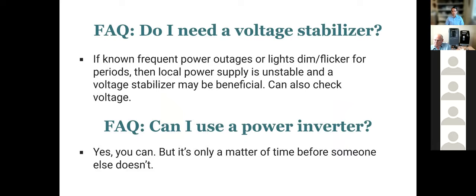So I mentioned this voltage stabilizer issue. A lot of people ask, how do I know if I need a voltage stabilizer? If the setting where the concentrator is going to be used experiences frequent power outages or commonly has issues with lights dimming or flickering for periods of time, then there's a pretty good chance that the local power supply is unstable and could cause some damage to the device over time. And so using a voltage stabilizer is likely to be beneficial. You can also check the voltage. And I'll defer to Robert, who can comment on that in a little bit.